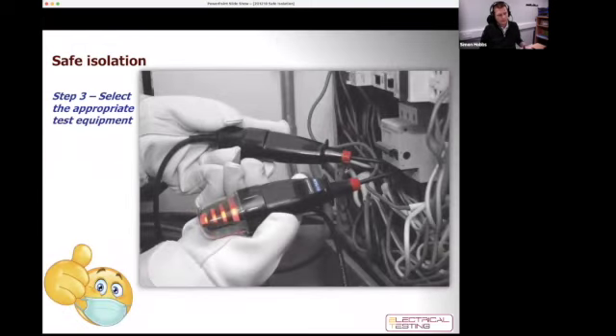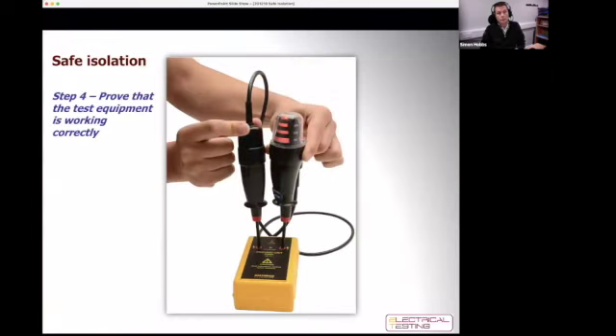We must select the appropriate test equipment. A voltage indicator, a test lamp, a neon contact device, similar to something that's shown in the picture here. And of course, they should comply with GS38, which is the Health and Safety Executive's guidance on test equipment and the associated British standards that go with that. So having selected the appropriate test equipment, we now need to make sure that it works. Typically, we may use proving units, such as shown here, but ultimately we need to prove it on any known live source. So as long as I've got a low voltage source that I know is live, I can use that.